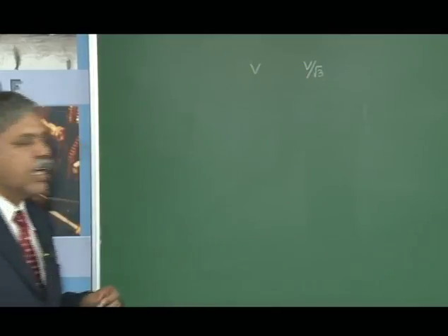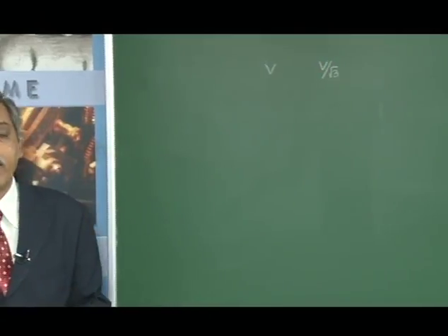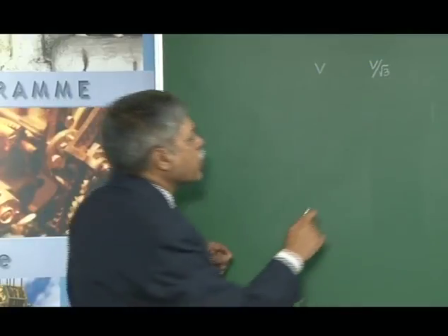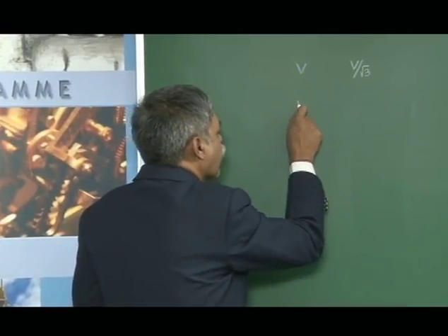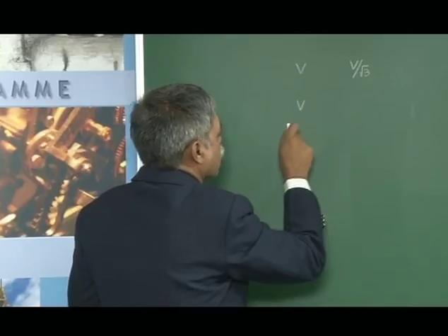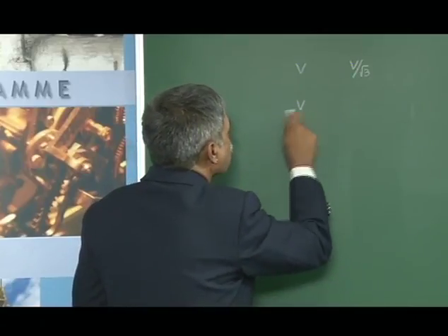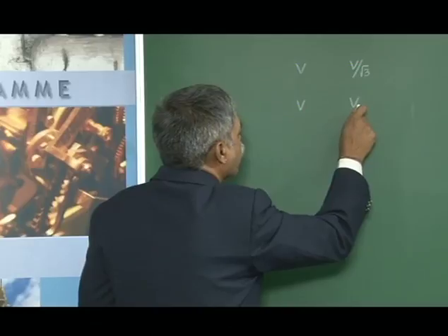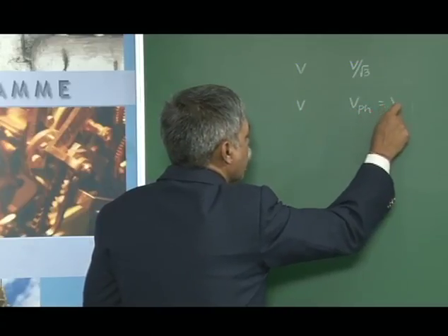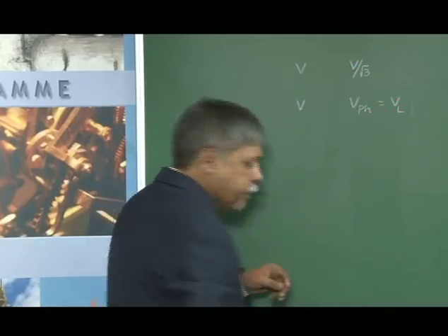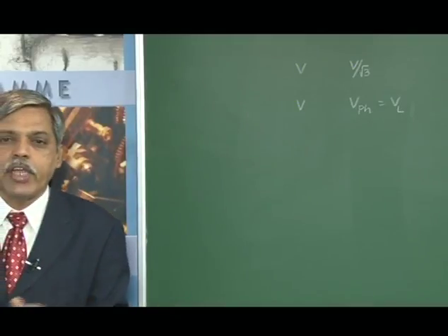So, because of this, the current drawn by the motor decreases. Once the motor windings are connected in delta, the full voltage will be applied across the delta connected stator, because in the delta connection the value of the phase voltage and the line voltage are both equal. So, this is how reduced voltage will be applied across the stator winding at the time of starting, and once the motor picks up the speed, we can change the connection from star to delta, thereby increasing the voltage.